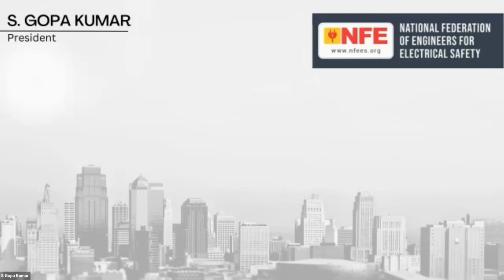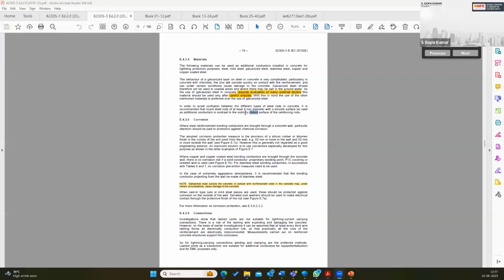Actually, I would say this is dangerous, because the lightning protection standard recommends using a down conductor with a smooth surface. If you are using rebars, the surface is not smooth, it is a ribbed surface. You can find this in IEC 62305 part 3. Just open the standard and search for "ribbed". I will share my screen and show you what is written. One moment, please. I'm sure you are able to see this. Yes.